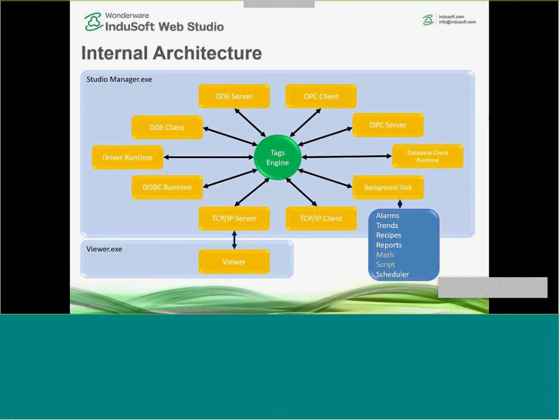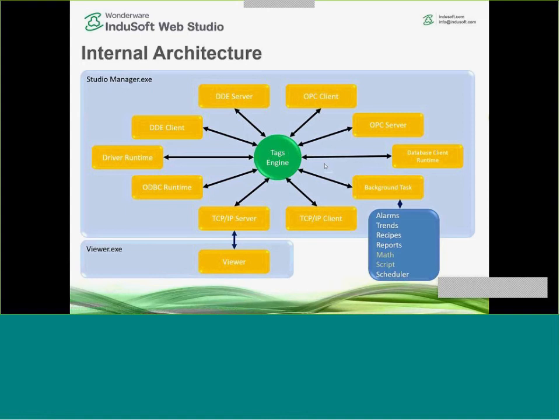Let's take a look at the internal architecture of the product to better understand how our features and tools work. We have a main core called the tags engine — our tags database and several other tasks that are connected to each other through that database. If we use our communication driver to get data from a field device, we get the data and throw it to the tags database. From there we can generate alarms, save trend history, or send data to our TCP/IP server for visualization on our local viewer, web sync clients, mobile access, or any visualization tool we have.